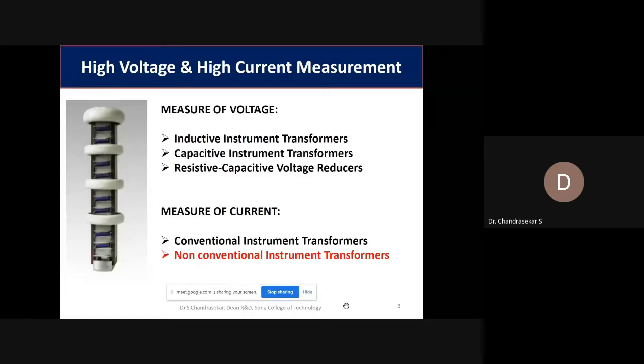The very common technique to measure high voltage is to use simple divider circuits. This simple circuit theory is followed in many places. If you use a simple resistive divider or a simple capacitive divider, you can easily measure the high voltage. And if you use a combination of resistive and capacitive dividers, we can also easily measure high voltages. For measuring currents, we can go for current transformers with a low secondary rating, so that you can easily measure the currents. Okay, but these are all very conventional measuring techniques, and these instruments mostly deal with low frequency.